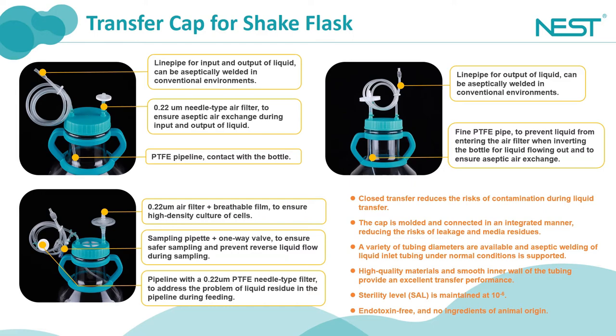What are the advantages of the multifunctional transfer cap compared to the two transfer caps mentioned above? It has an additional function of cell culture. For the two transfer caps introduced above, it is required to replace them with breathable caps for cell culture after completion of liquid transfer. As for the multifunctional transfer cap, cell culture can be started directly after completion of liquid transfer. The cover is equipped with a breathable membrane and an air filter with totally sufficient oxygen flux. Moreover, the multifunctional cap also possesses a sampling function. The sampling tubing is composed of a sampling valve and one-way tubing, and the one-way valve guarantees only outflow to ensure safer sampling.